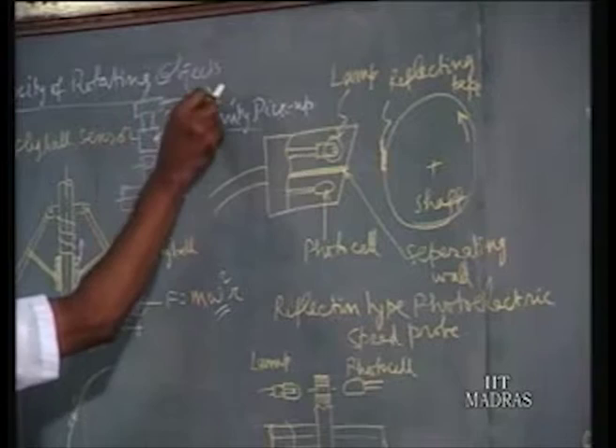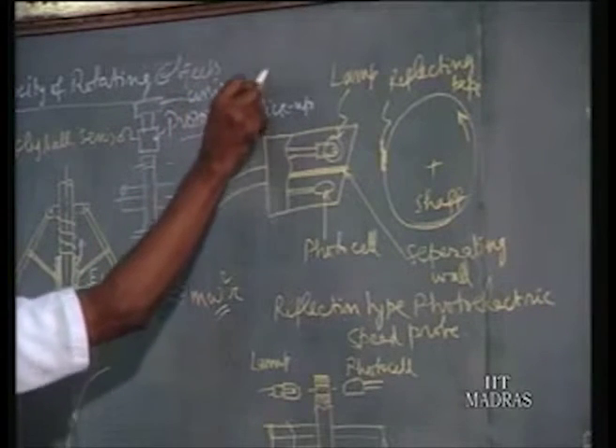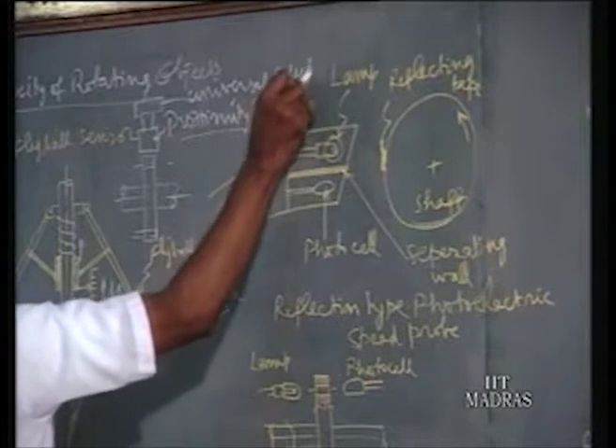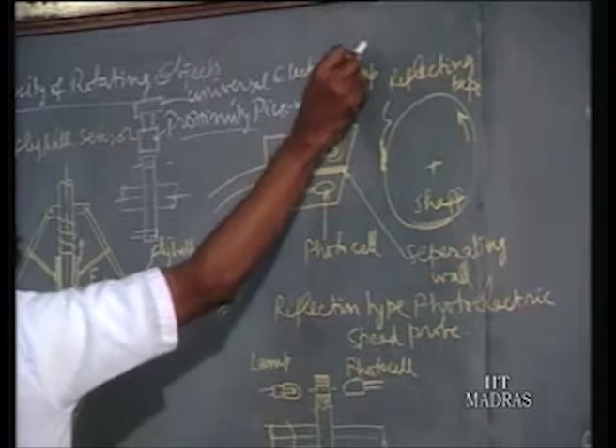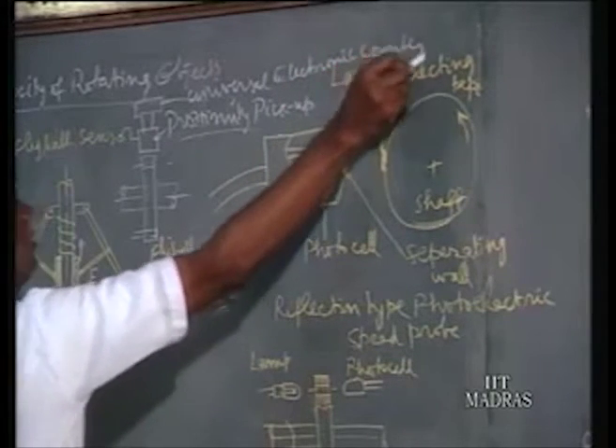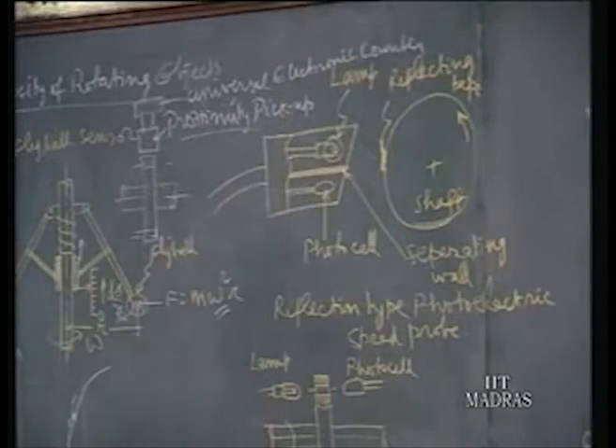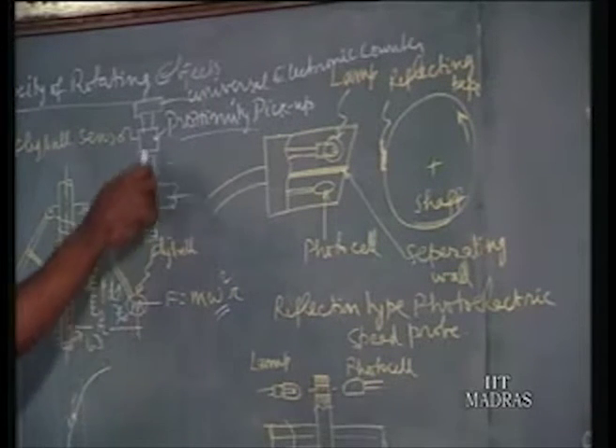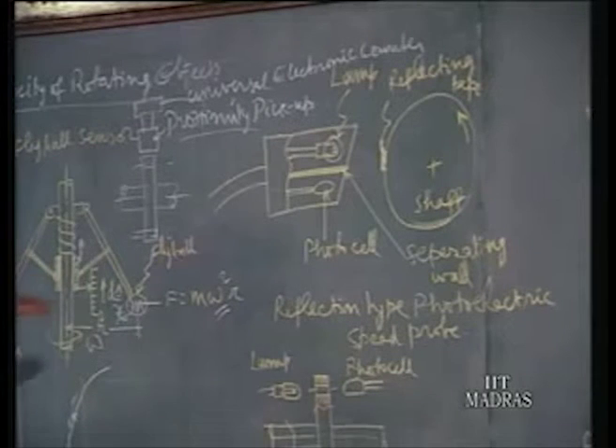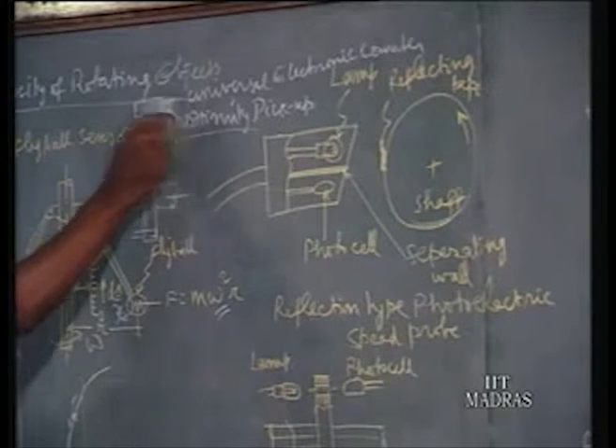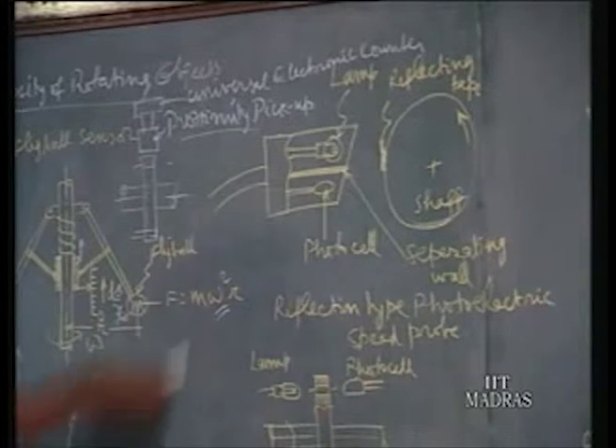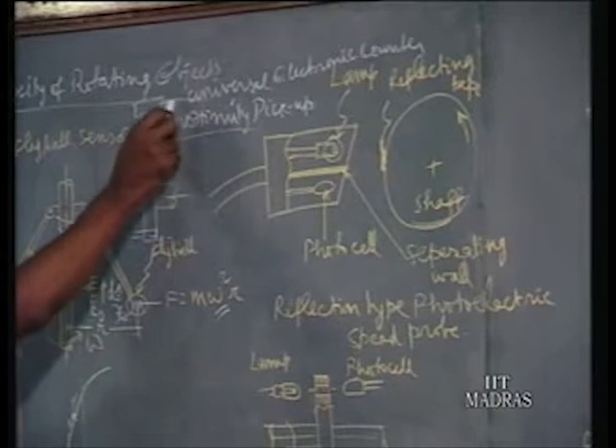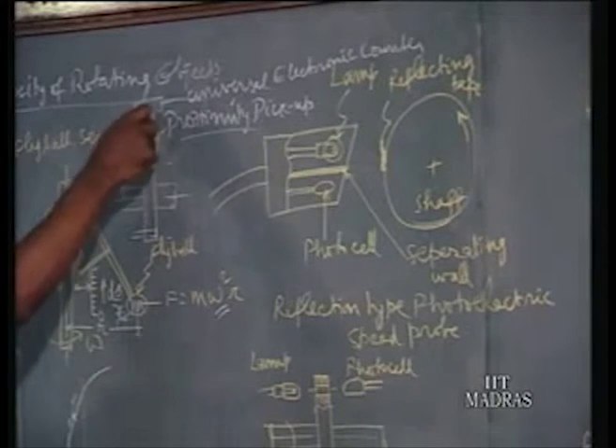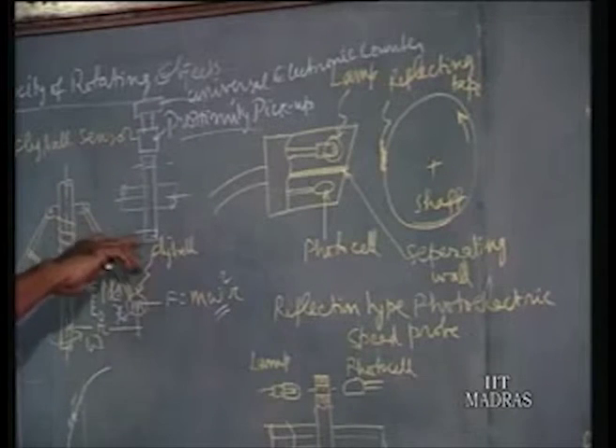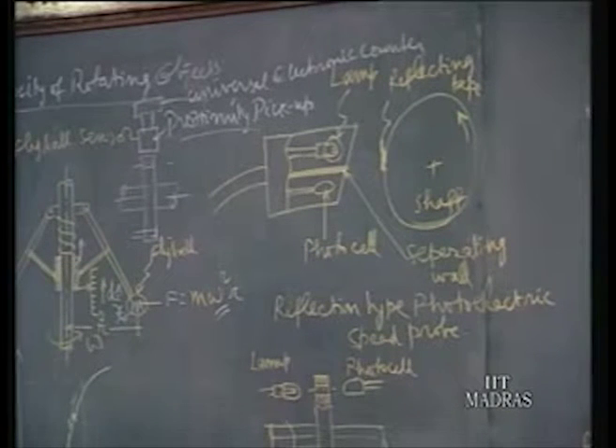universal electronic counter, where the pulses can be counted per second. So per second, so many pulses will be there. That divided by 10 will give the RPM per second. Suppose you can select a different time base, 1 second or 10 seconds, whatever it is. If you select 1 second, whatever the pulse count, it will count it, and if you divide by 10, that will give the rotating speed per second.